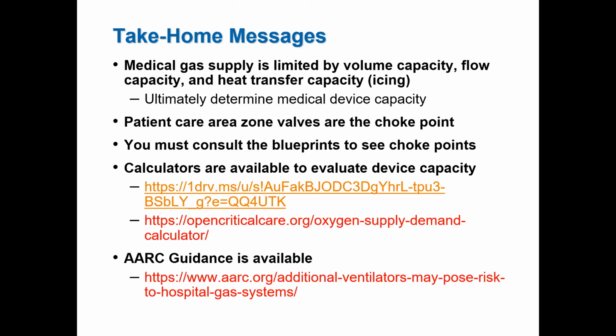And I think about the ventilators that we talked about. I'm going to assume you have a number of LTV 1200s. If you do, make sure you turn the bias flow off. Otherwise, it's 10 liters a minute during the expiratory flow. And think about that with all your ventilators that have an expiratory bias flow. Now, some of it might impact the triggering a little bit, usually negligibly, but that's one way to save oxygen. Again, Rob mentioned, I can't tell you how many people I have told that high flow nasal cannula uses far more oxygen than the ventilator does.